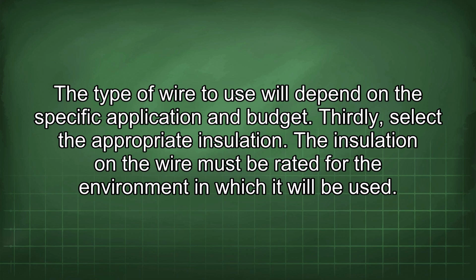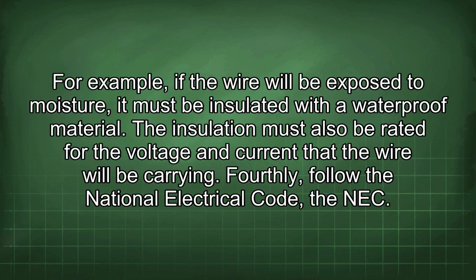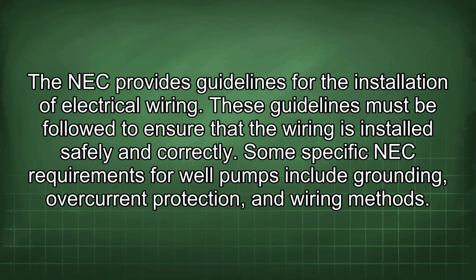Thirdly, select the appropriate insulation. The insulation on the wire must be rated for the environment in which it will be used. For example, if the wire will be exposed to moisture, it must be insulated with a waterproof material. The insulation must also be rated for the voltage and current that the wire will be carrying. Fourthly, follow the National Electrical Code, the NEC. The NEC provides guidelines for the installation of electrical wiring. These guidelines must be followed to ensure that the wiring is installed safely and correctly. Some specific NEC requirements for well pumps include grounding, overcurrent protection, and wiring methods.